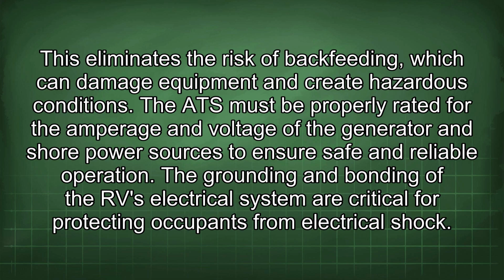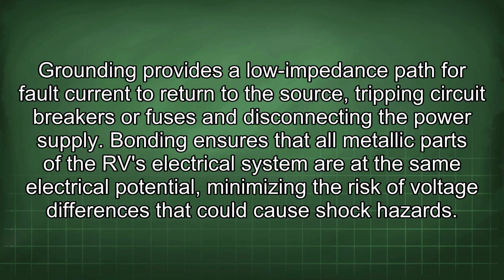The grounding and bonding of the RV electrical system are critical for protecting occupants from electrical shock. Grounding provides a low impedance path for fault current to return to the source, tripping circuit breakers or fuses and disconnecting the power supply. Bonding ensures that all metallic parts of the RV electrical system are at the same electrical potential, minimizing the risk of voltage differences that could cause shock hazards.